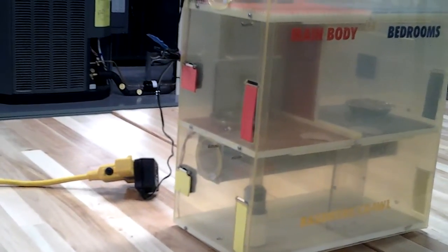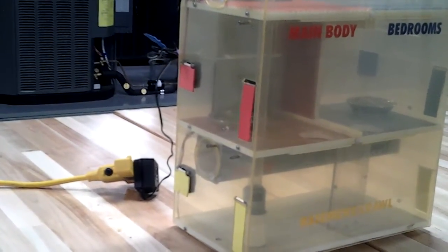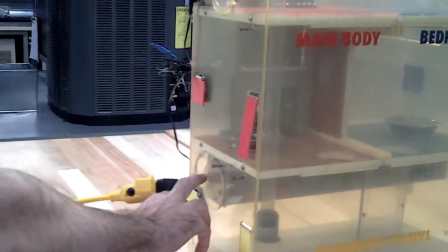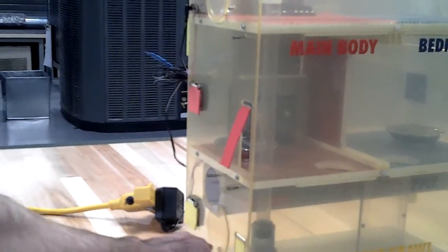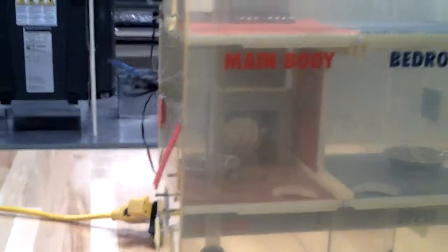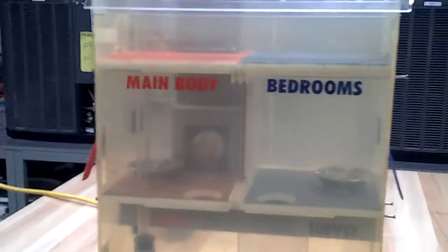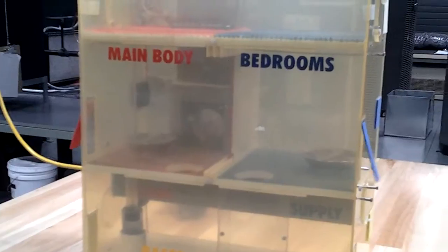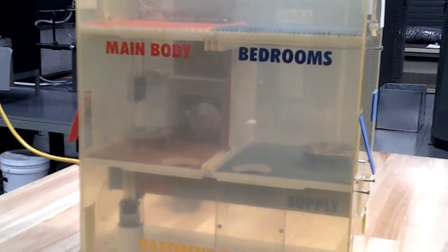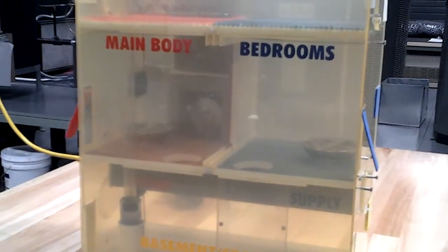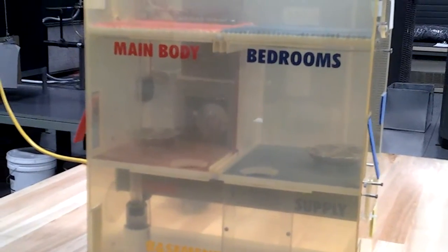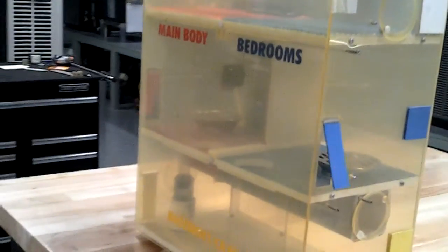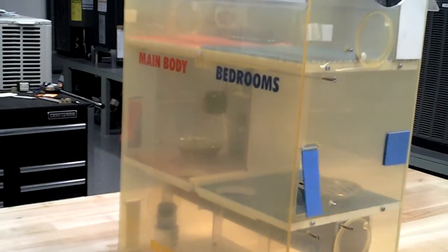Adversely, return duct leaks that draw air from the outdoors can cause positive pressures within the house. Here we're introducing outdoor air into the return duct. For every CFM that is gained through the return duct, or through a supply or return leak for that matter, a CFM will then exfiltrate through the cracks and holes in the structure, whether it's a window, a door, a hole in the roof. It does that in an attempt to equalize the newly introduced positive pressure.